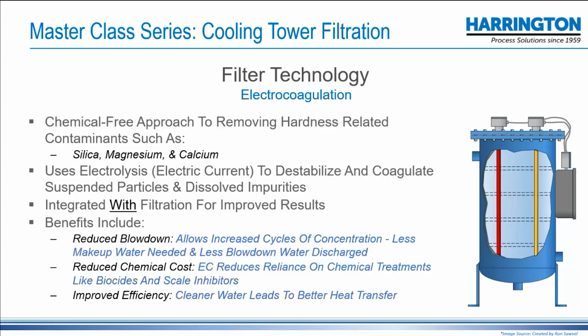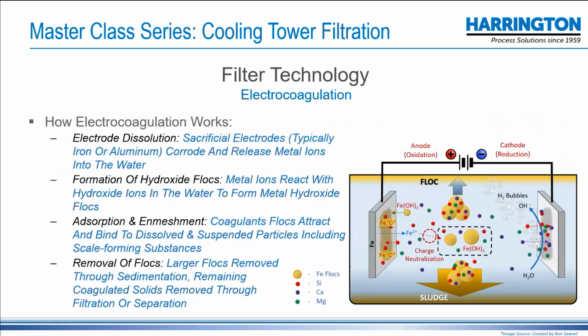So it'll release iron or aluminum ions into the water, which will congeal with the solids and form a floc that'll drop out. And in fact, it'll drop out into the bottom, but the ones that are still entrained will be so easy to filter, it'll highly increase your filtration efficiency. But above and beyond that, it takes out the three bad boys of scale, and that's silica, magnesium, and calcium. And of course, there's an energy demand, not high.